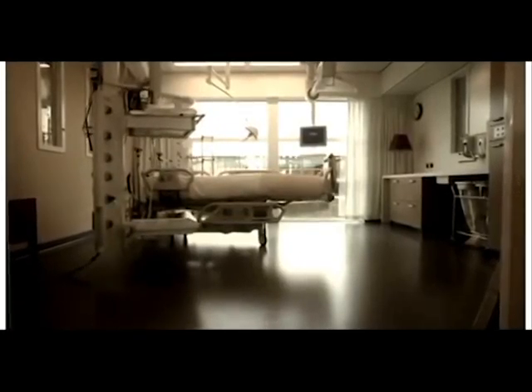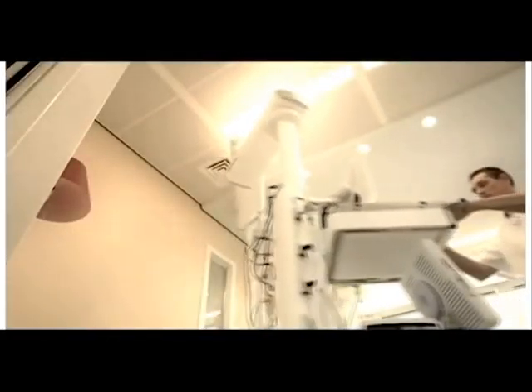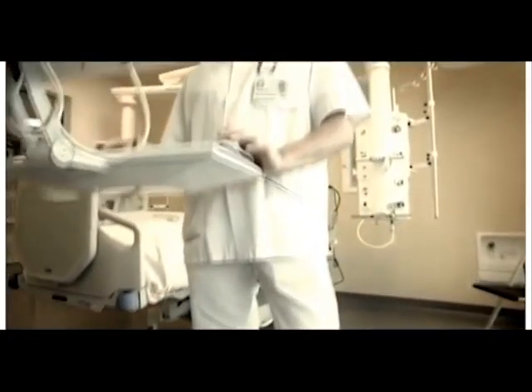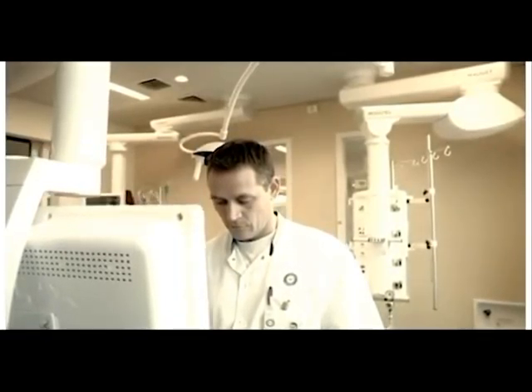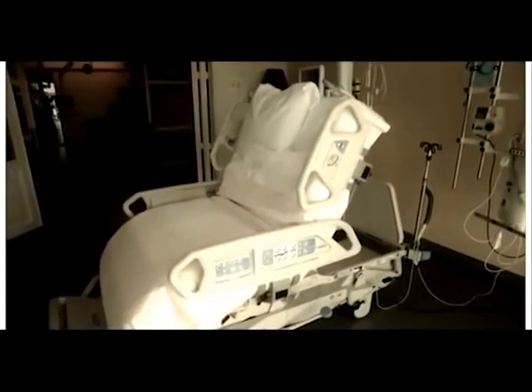The proposed solution is the power column. It is a manufactured utility and equipment mounting column fixed at the ceiling and leveled to be effectively used for the patient. It contains many configurations of power supply, medical gases, vacuum, communication ports and monitor mounts. It has a very small footprint in the room and is normally positioned diagonally behind and to the side of the patient's head.